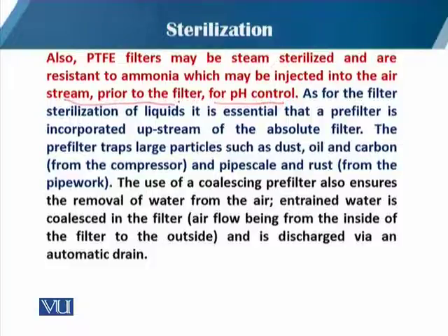As with the filter sterilization of liquid, it is essential that a pre-filter is incorporated upstream of the absolute filter. The pre-filter traps large particles such as dust, oil, and carbon, which mostly come either from the air or from the compressor, as well as pipe scale and rust. Because when there is some mechanical work, there can be scaling and rust particles that come along with the air.